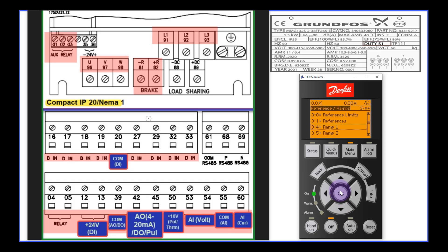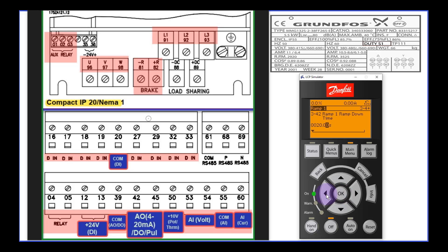After that, I select Ramp 1. I will select the ramp up time and press the OK button to change it — I will change it to 5 seconds. It depends on your process requirement. I press OK to accept the changes, then press the down arrow key to move to the next menu. The next menu is the ramp down time. I press OK to change it to 5 seconds, then press OK to accept, and press the back button until I see the main menu page.